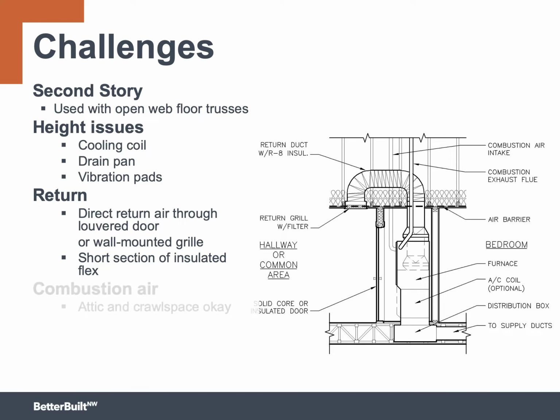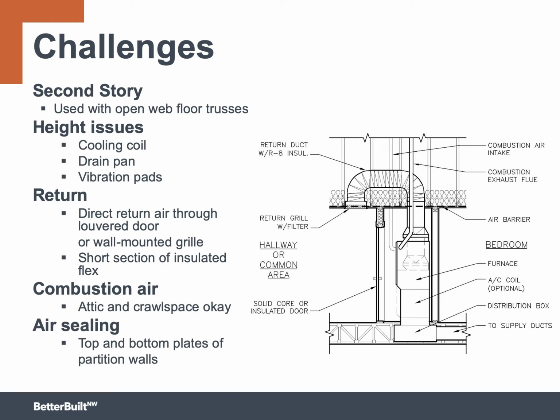You absolutely should use a sealed combustion furnace when located inside, and the combustion air needs to run to the outside. Don't forget to seal the faces of the top plates to the back of the drywall. This is usually accomplished by a strip of gasket material. Some form of seal is required by Energy Star and all the certification programs.